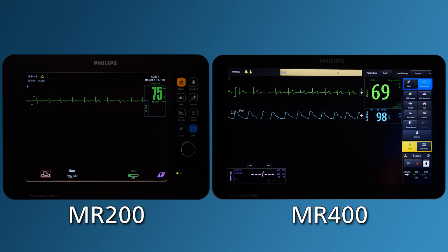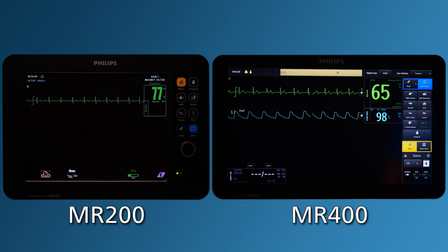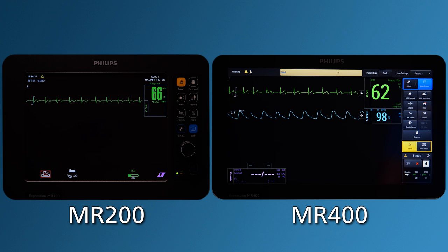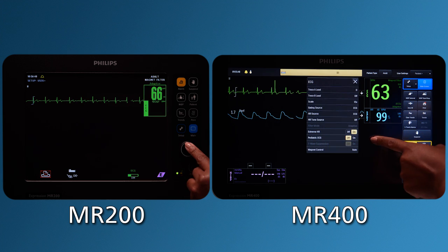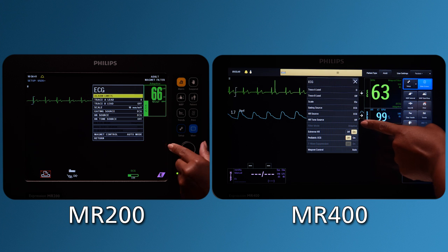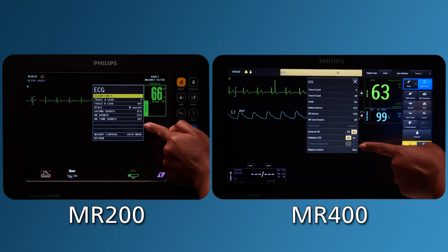the Philips MRI system filters the ECG and transmits that filtered waveform and heart rate back to the patient monitor for display. Note, with Magnet Control set to Auto, filter mode and T-wave suppression are disabled.